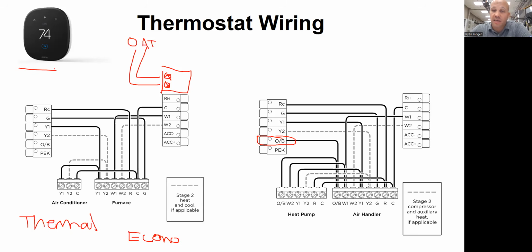If you have an Ecobee, it has that because all Ecobees do heat pumps, right? But not every thermostat you have on the wall does it. If you got an old stat from 20 years ago, it probably wasn't a heat pump if they didn't have a heat pump. You used to have to buy a thermostat that was specific for each application. Now you buy one thing and you program it for your application. So if they have a modern thermostat, let's say they replaced their thermostats 3 years ago, they probably have one that has a heat pump ability on it. If you're not sure, you pull it off the wall, you look for either on a modern thermostat, it would always say O/B. Old thermostats would have an O or B, two separate terminals. So you might need to replace the thermostat as part of the project, depending on what kind of thermostat you already have.